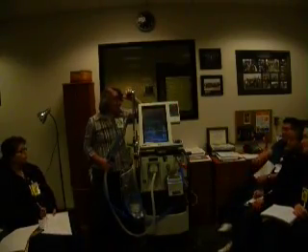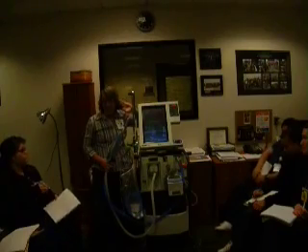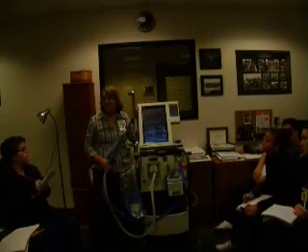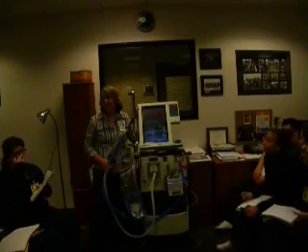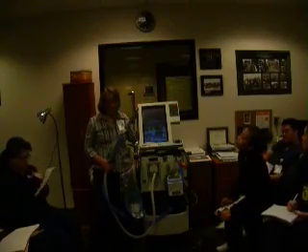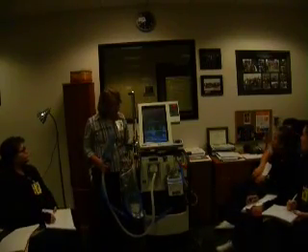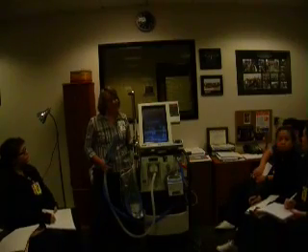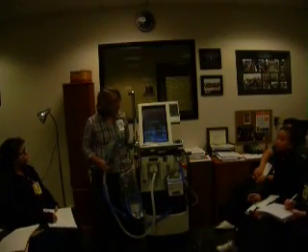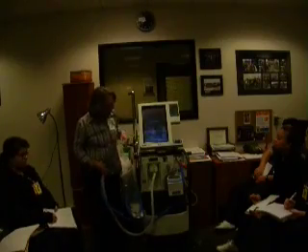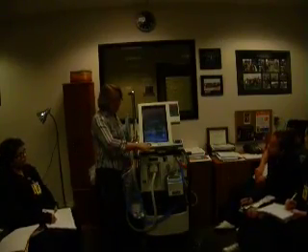That's not meant to take a patient outside around the parking lot. The battery is like an emergency until you can get to another power source. They do not last long. I think you could imagine that a battery inside a machine like this would not last very long. So it's very short. Down here on the bottom, you have volume.